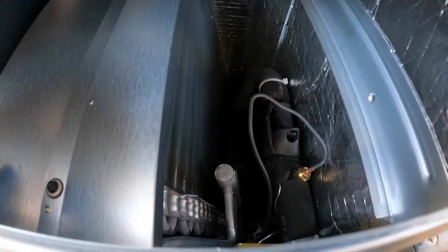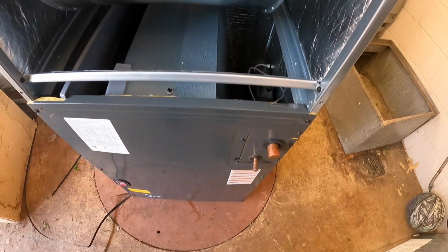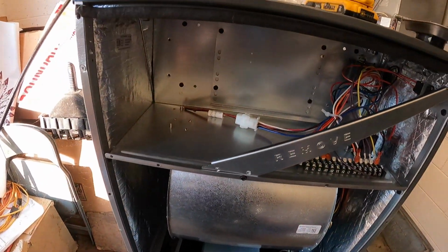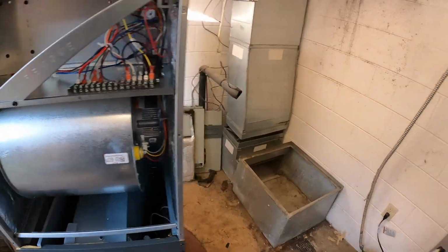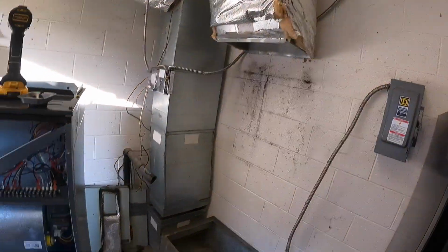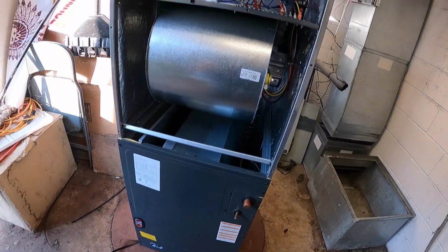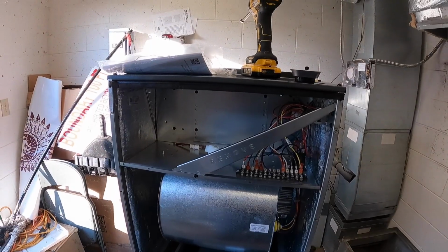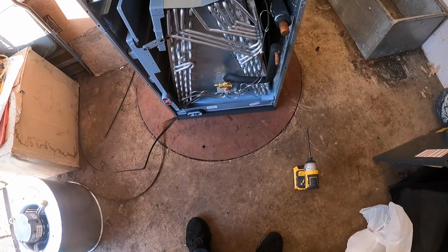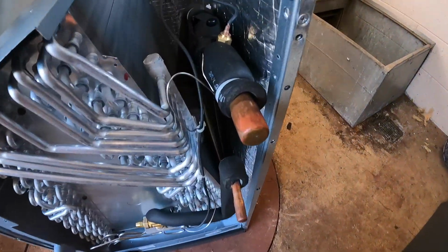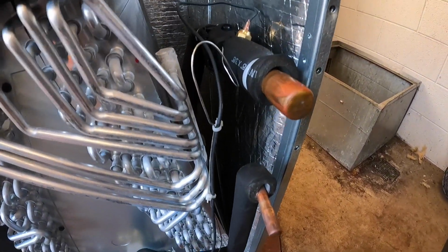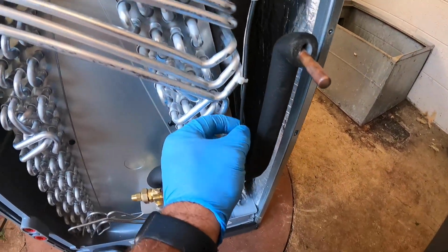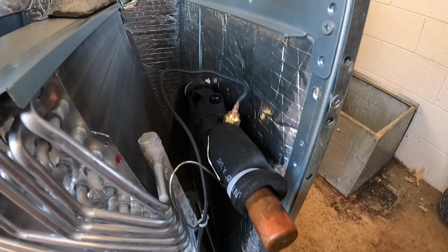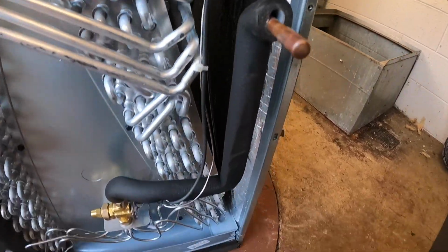So also looks like this equalizer tube for the TXV is aluminum, so we'll open that up down there and get a look at that too, because I'm going to have to take this thing apart. I can't pick this thing up and wrestle it into tight quarters like that without gutting it. Gives me a good chance to look at it. Well, good news, guys. It was just bad lighting. It's not aluminum. It's actually black. I've got one of the rubber heat shrink things on it, probably to keep it from rubbing somewhere.